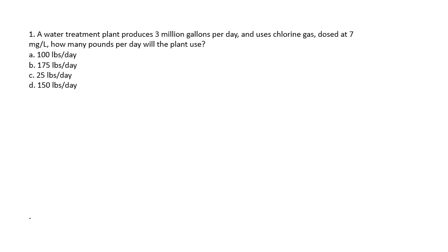Question number one. A water treatment plant produces 3 million gallons per day and uses chlorine gas dosed at 7 milligrams per liter. How many pounds per day will the plant use? A: 100 pounds a day. B: 175 pounds a day. C: 25 pounds a day. Or D: 150 pounds a day. Pause if you're going to work through this yourself, because I'm going to start working through the answer on the next slide.